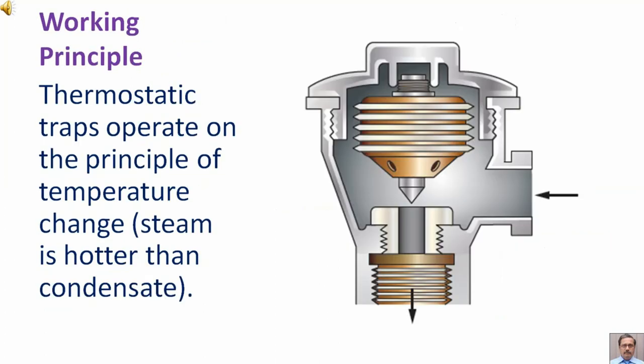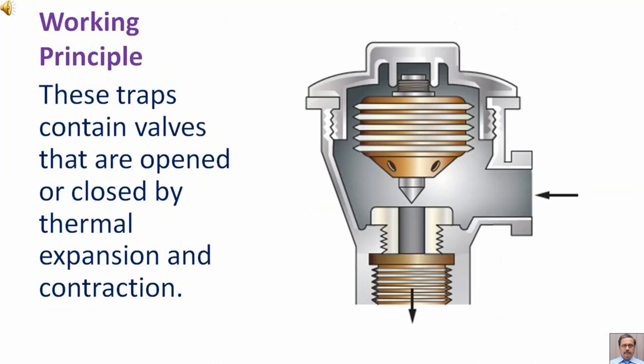Thermostatic traps operate on the principle of temperature change. Steam is hotter than condensate. These traps contain valves that are opened or closed by thermal expansion and contraction.